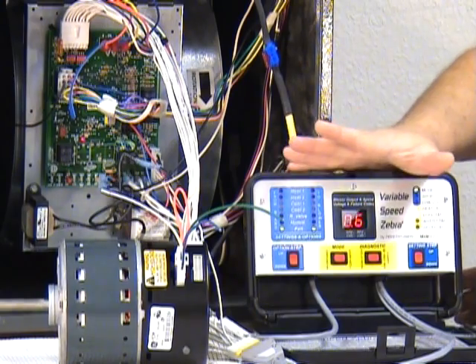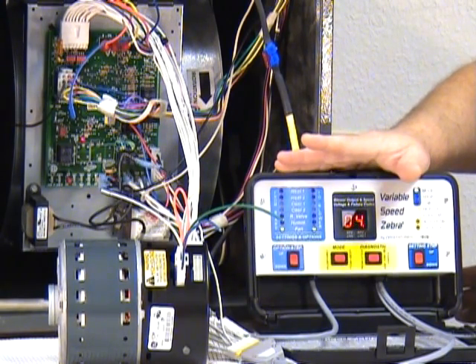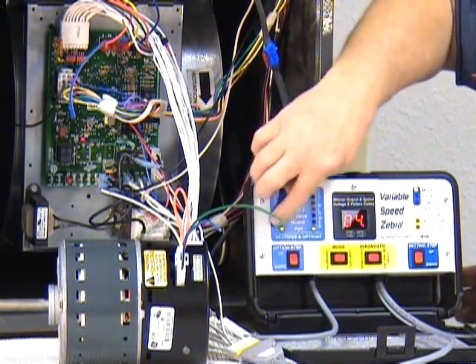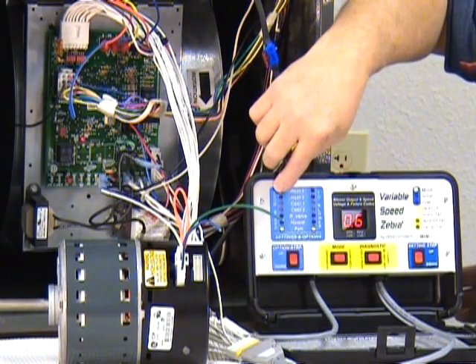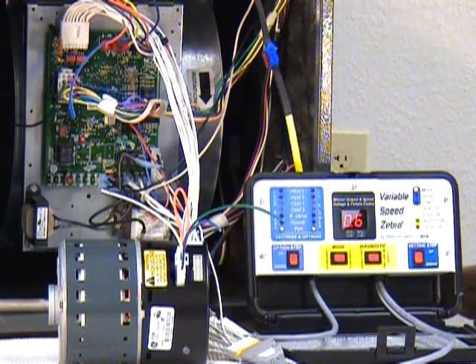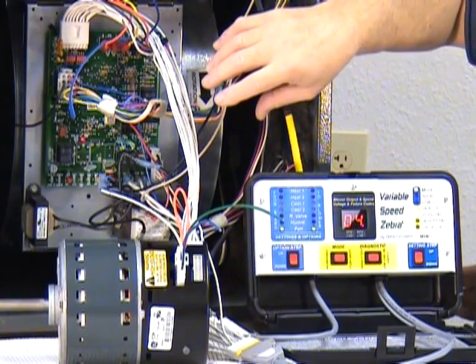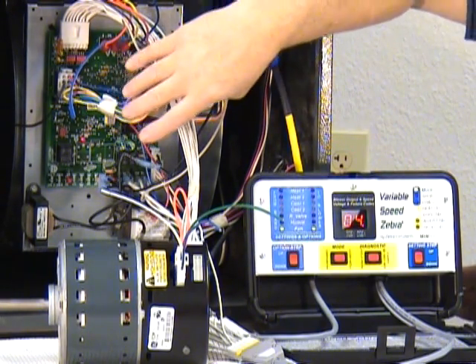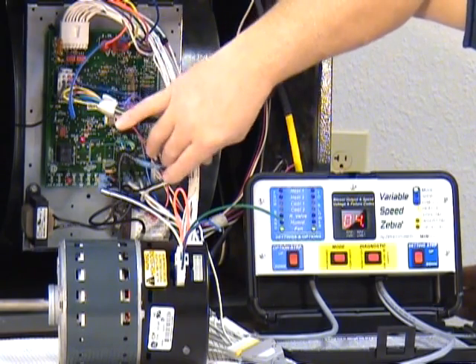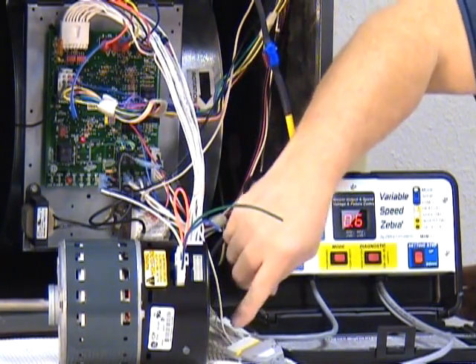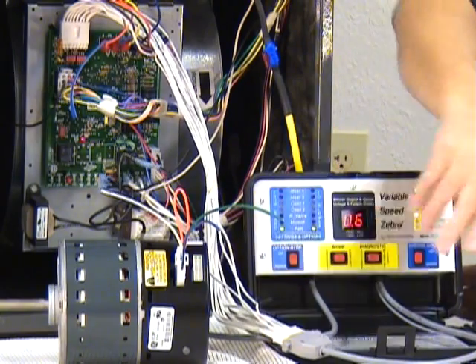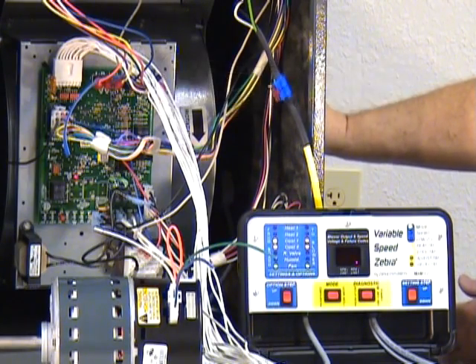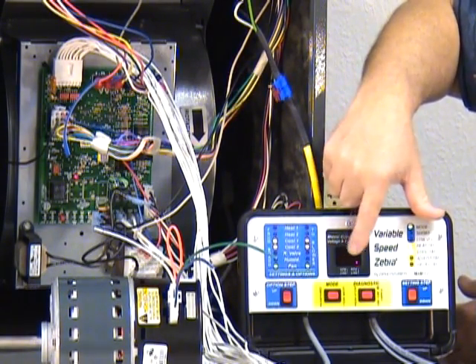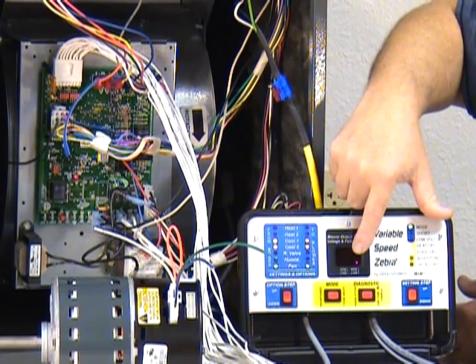Basically what this is going to do is tell you where the problem is in your system. If you don't have any signals coming down to this side, and your thermostat has sent the signals to the board, then it's either telling you your problem is on the board or in the harness that comes from the board to the motor, which right now you have connected up to the variable speed Zebra. I've gone ahead and disconnected the power line going into that motor so it won't make so much noise as we're talking today. So you won't see a CFM and RPM display as we make some changes.